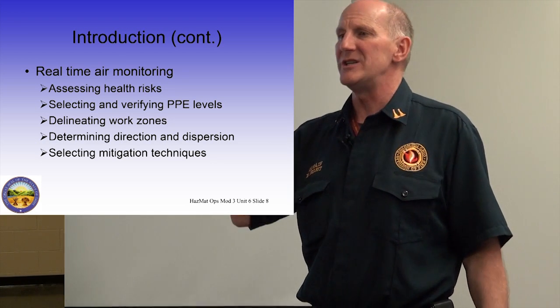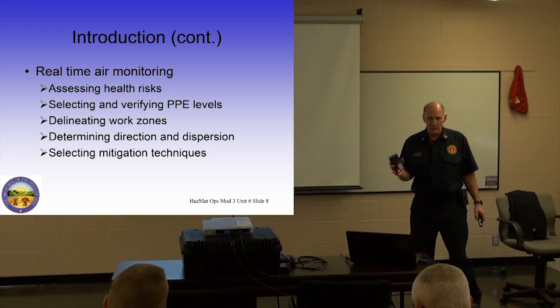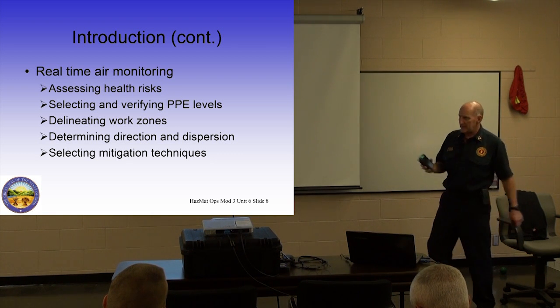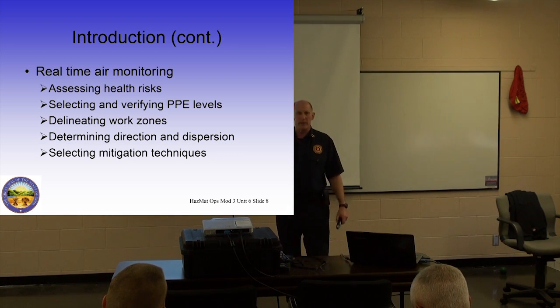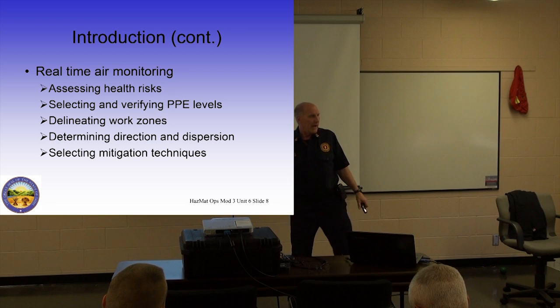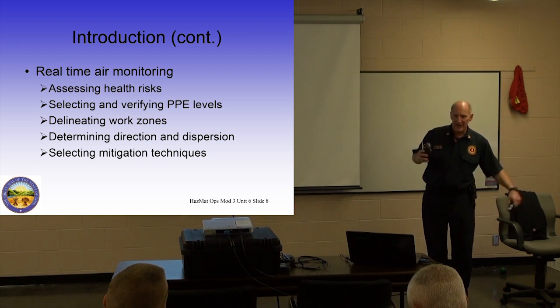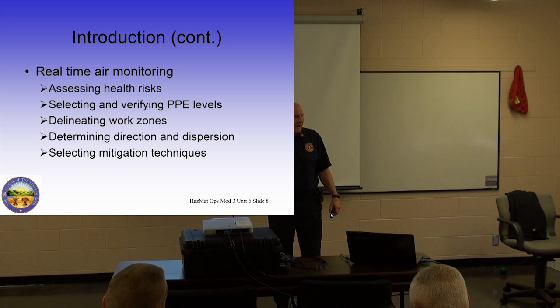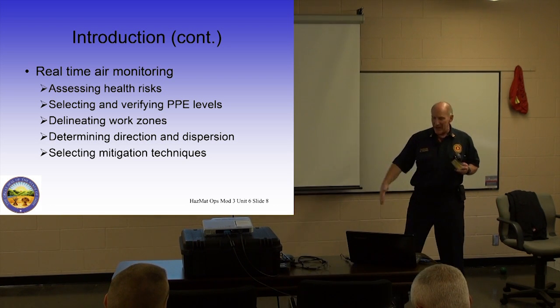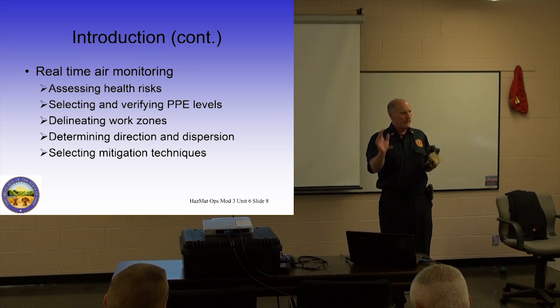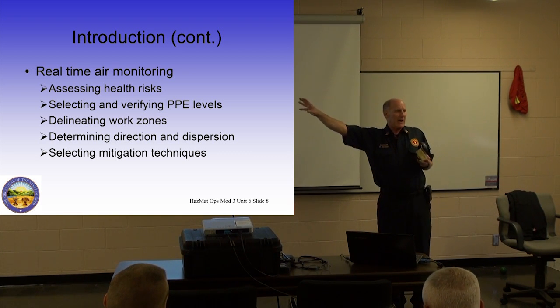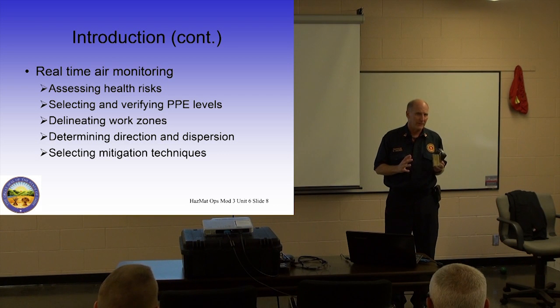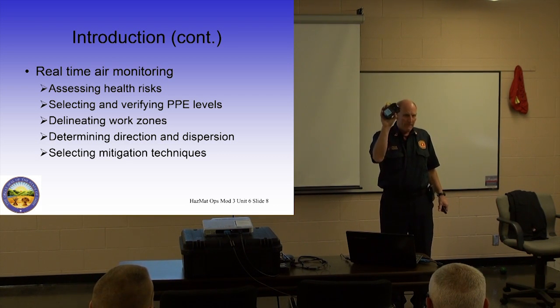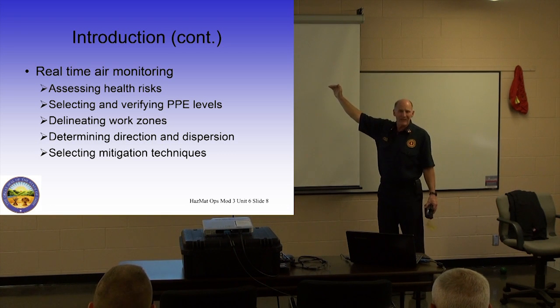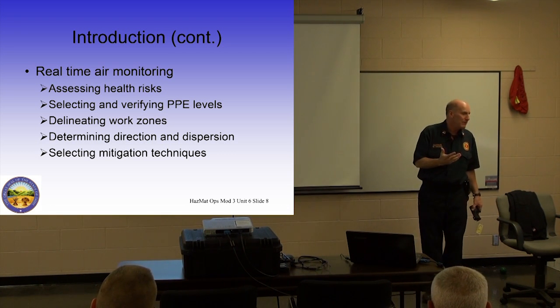I can also use it to figure out my work zones. So if I get a reading of 0 here, and I take 3 steps forward and I get a reading of 3, whoa, okay. Well, why did I do that? And I step back and I don't get any reading, and I step forward and I get a reading of 3, and I step back and I don't get any reading, then you can see I could easily draw a line right here, put up a piece of barrier tape and say, hey, that's my hot zone, this is my cold zone. And so I can delineate the work zones by using the air monitor to figure out exactly where the chemical or where the problem might be.